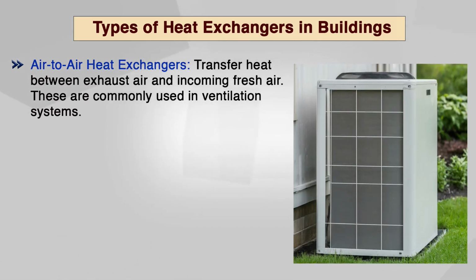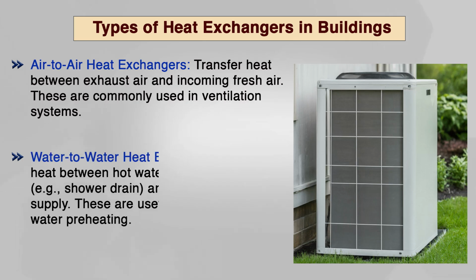First is air to air heat exchangers. These workhorses capture heat from exhaust air, which is typically warmer than the incoming fresh air, and transfer it to the incoming air stream. This preheats the incoming air, reducing the heating load on the system, especially during winter. Air to air heat exchangers are a popular choice for ventilation systems.